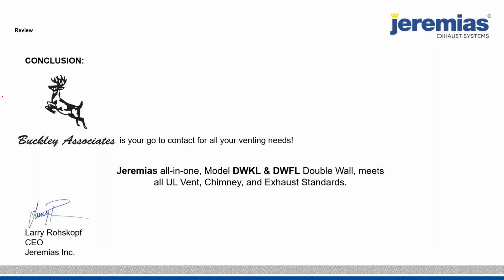Okay, so one thing is zero clearance grease duct. I understood that it acts as its own shaft, so that means I wouldn't have to have a separate rated shaft for other things. I could put this in the same shaft and not have to have a separate shaft? Correct. But in a lot of cases, they actually use it by itself, and then the shaft around it is not really a fire rated shaft. It's just a single drywall wall that to have access to the grease duct just requires a standard door type of setup, not a fire rated door. So do keep that in mind as well.